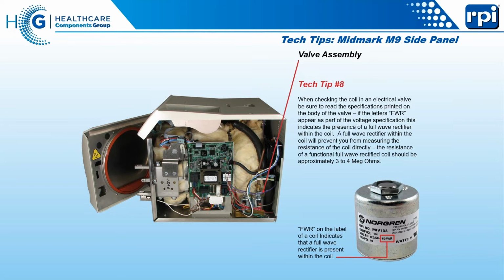So they realized that another way they could go about doing that was, instead of just applying straight 120 volts to these valves, they built a full wave bridge rectifier into the coil of the valve. And what that does is it takes the AC, clips it off, so you're kind of looking at pre-smooth DC, which takes some of the buzz out of the valve and takes the heat out of the valve, because it isn't bouncing up and down 60 times a second. The parts for a valve that is full wave bridge rectified versus the parts for a valve that is not full wave bridge rectified are not interchangeable. So it's always a good idea to know which kind of valves you got. If you do mix that up, your valve will buzz. That's not the worst thing in the world, but it's really annoying.